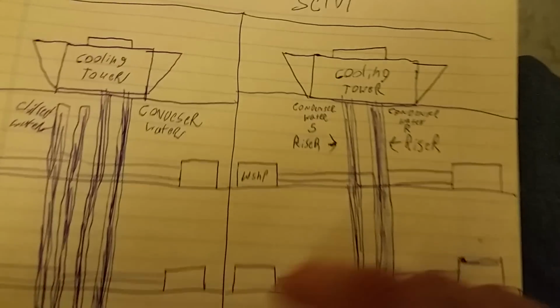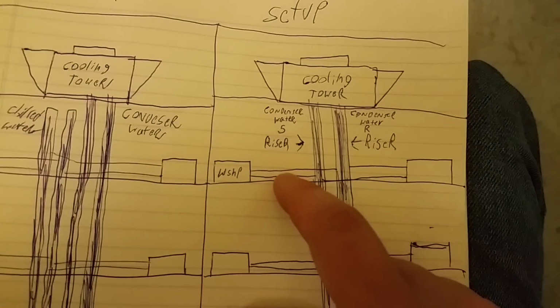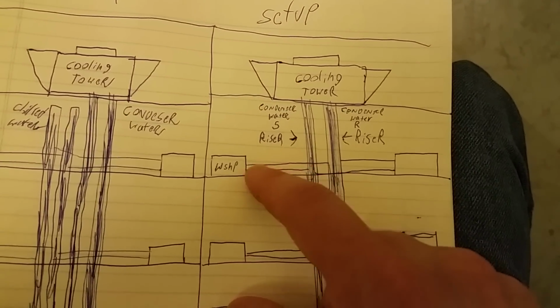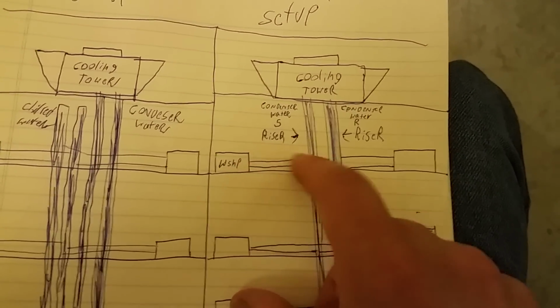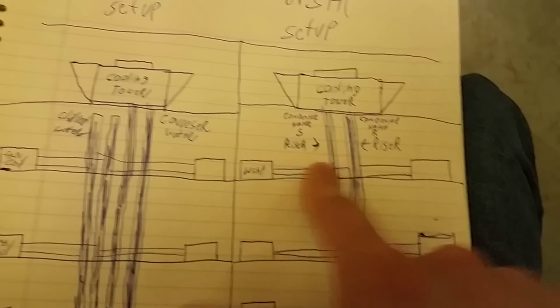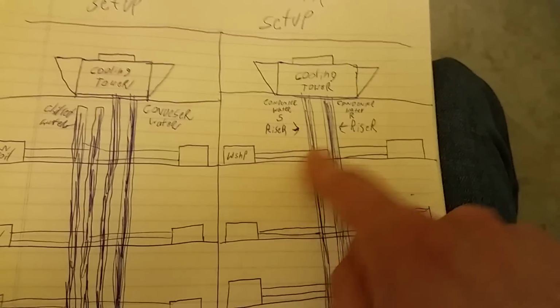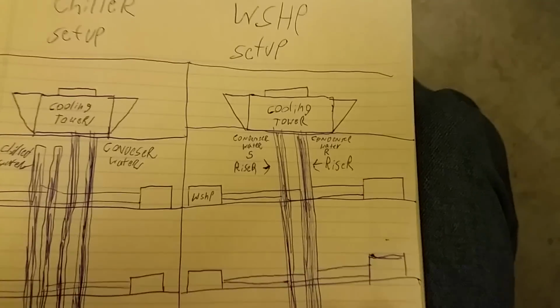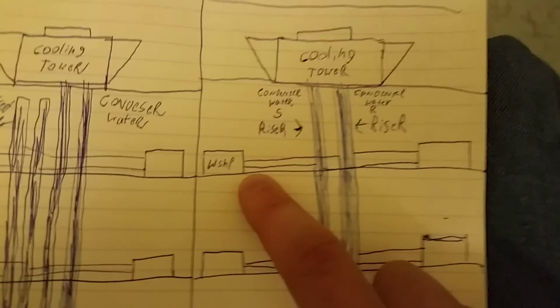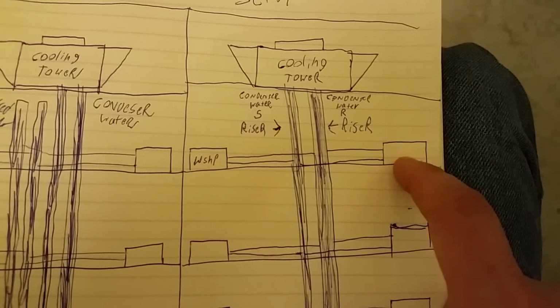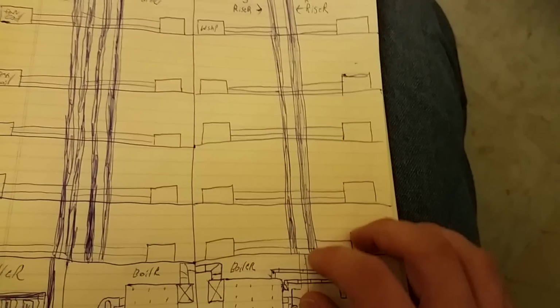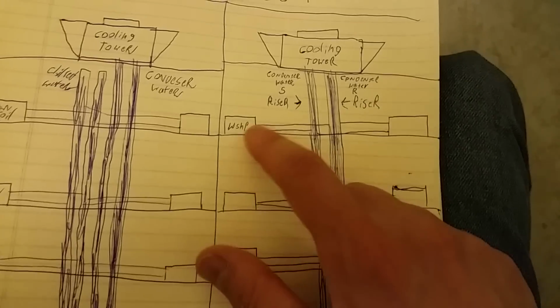Some of these little units, sometimes, if they're not getting enough water, they will put little circulators on here just to push it around if the line is clear and it's just not getting enough flow. Some of these pumps are also on VFDs. You may have to raise the frequency. Anyway, each floor has a little water source heat pump. And it's really simple. You could get it just by looking at this.